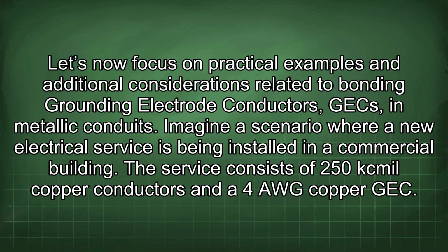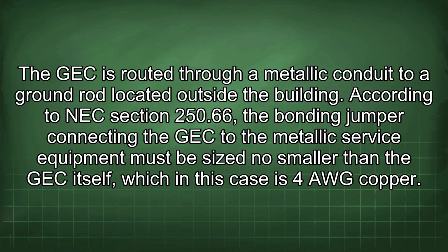Let's now focus on practical examples and additional considerations related to bonding grounding electrode conductors, GECs, in metallic conduits. Imagine a scenario where a new electrical service is being installed in a commercial building. The service consists of 250 kcmil copper conductors and a 4 AWG copper GEC. The GEC is routed through a metallic conduit to a ground rod located outside the building.